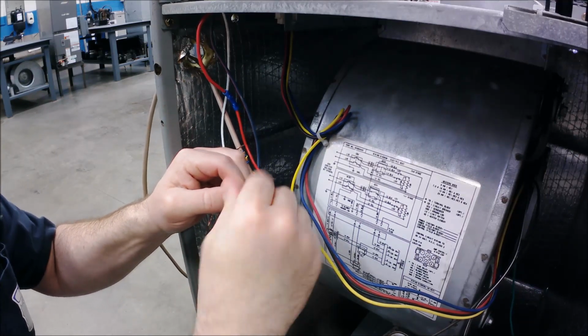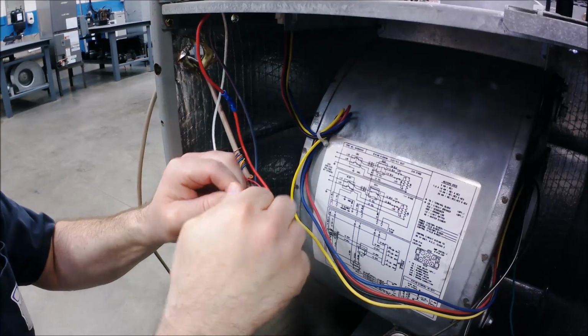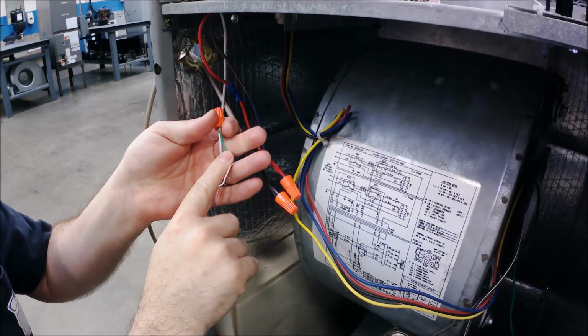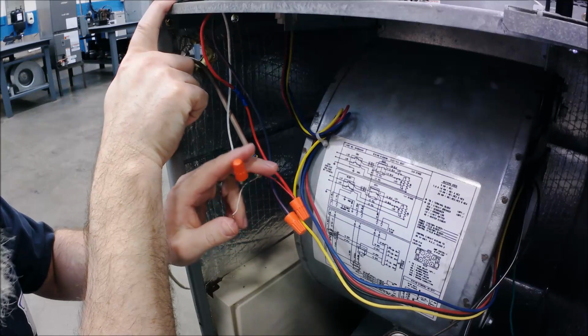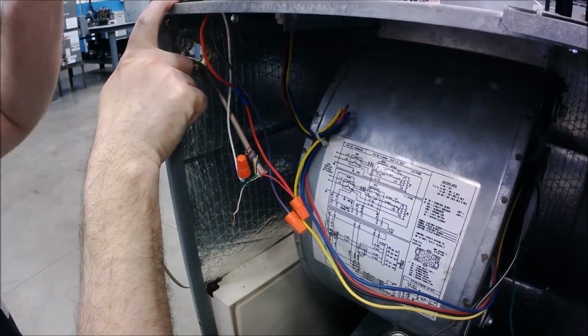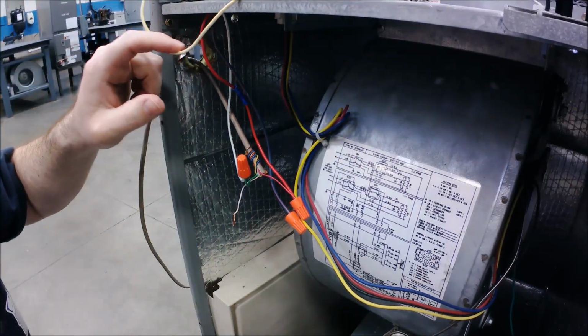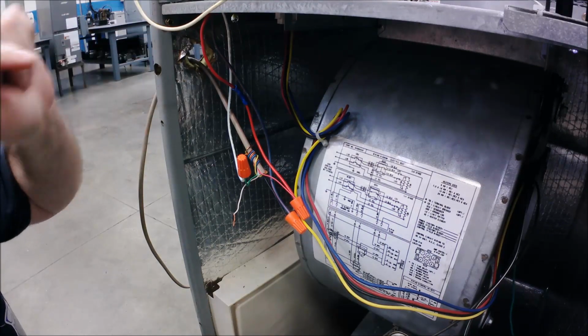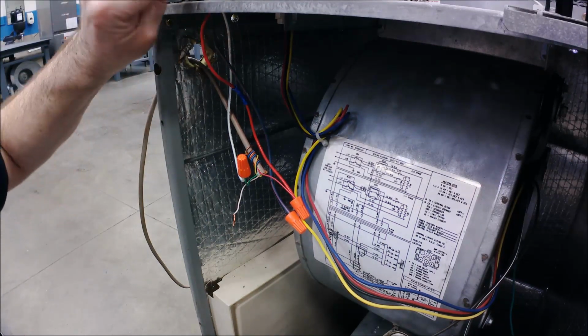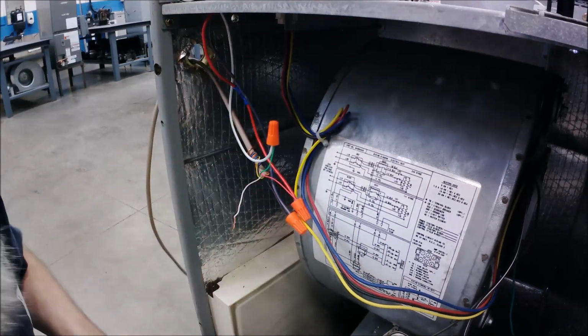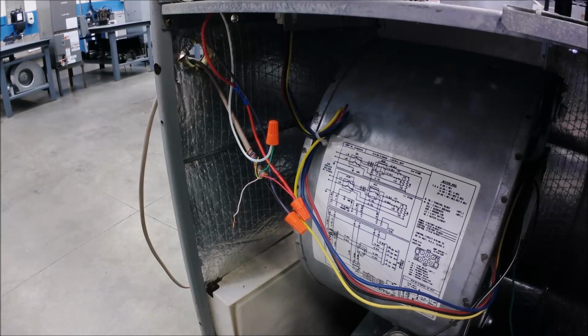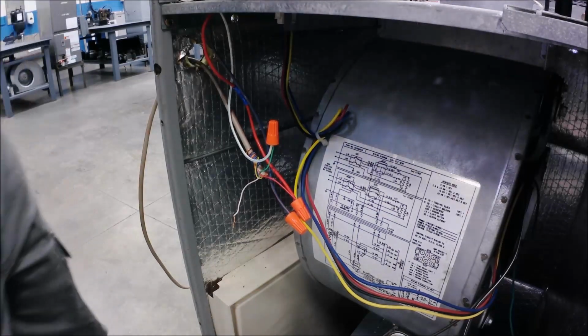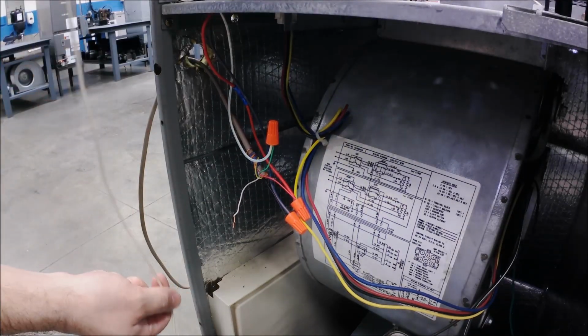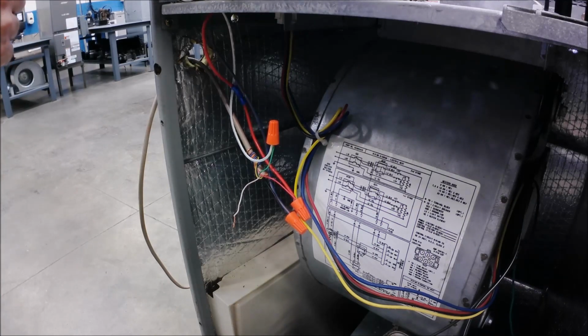So I'm going to do that low voltage connection there, and when the thermostat sends power out on G, then it's going to energize the coil of that rib relay, and then we've already tied in our white yellow, which is the common for the rib relay coil. So that connection is previously done. All right. With the white, as I said, we're going to start from scratch. So I'm going to run a white wire down through this little bushing area.